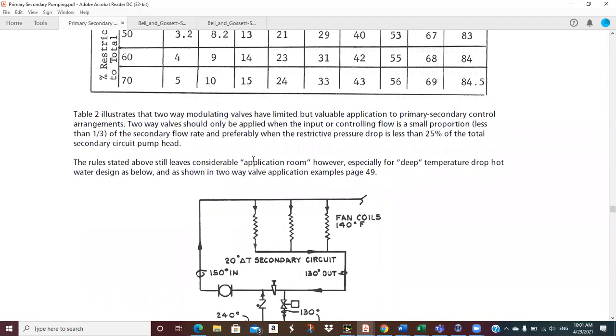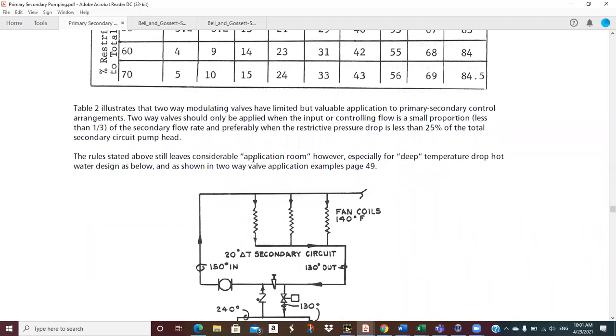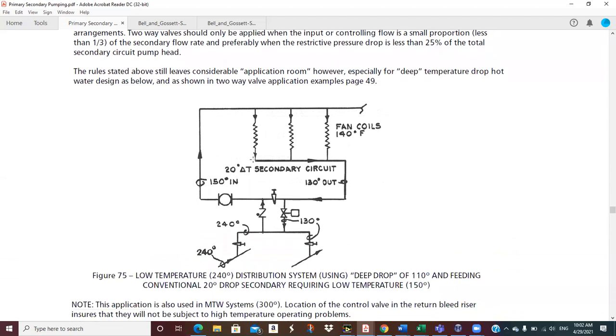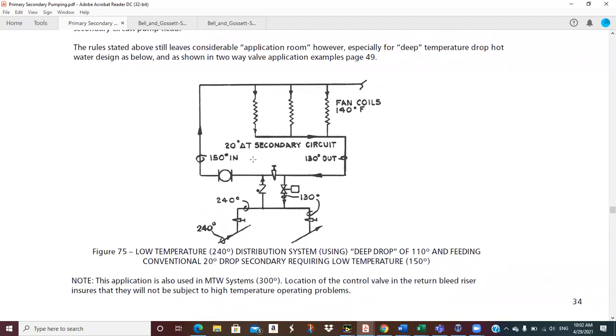So just to pound it home again, Table 2 illustrates that two-way modulating valves have limited but valuable application to primary-secondary control arrangements. Two-way valves should only be applied when the input or controlling flow is a small portion, less than, say, a third, so 33% of the secondary flow rate, and preferably when the restrictive pressure drop is less than 25% of the total secondary circuit pump head. Just let that sink in for a minute. Make sure that you're good on those, because some of you could wind up in a position of doing some of this, and you sure want to understand what you're doing.